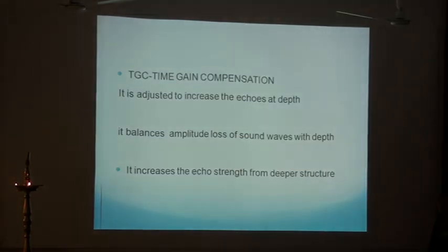Time gain compensation is another mode. As I told you, as the waves are going down, they are getting attenuated. So to increase the echo strength from deeper structures, we use this knob of TGC, and we can increase the amplitude of the waves.